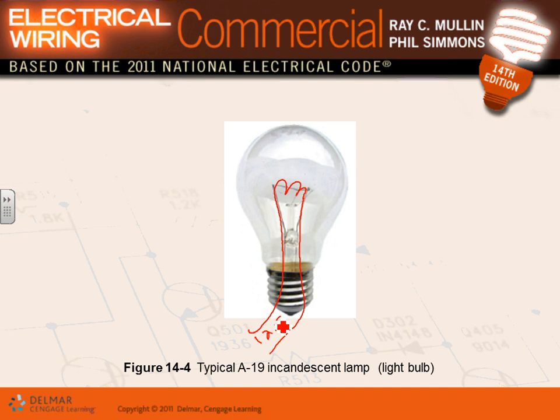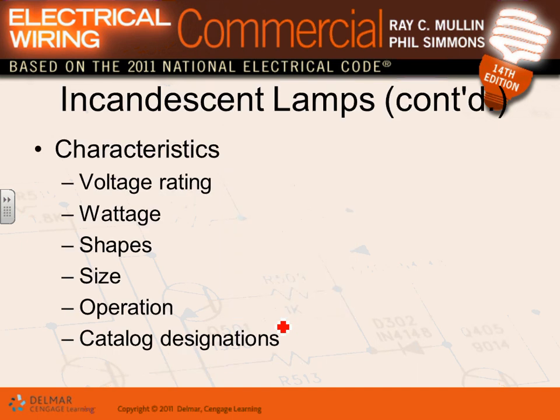Incandescent lamp characteristics: they come in different voltages, wattages, different shapes and sizes. Operation life is about 1000 hours — really poor. They have different catalog designations for shapes and can come at low voltage — 12 volts, 6 volts, or 24 volts — as seen in refrigerators and other applications besides buildings. They will continue to exist in other applications where they make sense.